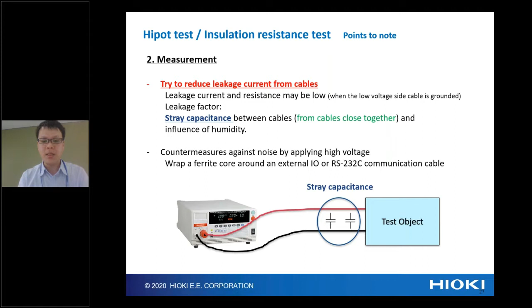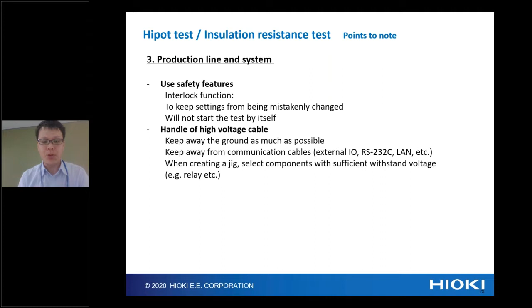Thirdly, production line and system. Our Hipot test and insulation testing has an interlock function for safety, so please use it to keep settings from being mistakenly changed. Okay, and handling of the high voltage cable: keep it away from the ground as much as possible, as I told you, like this. So please be careful, especially with the red cable.